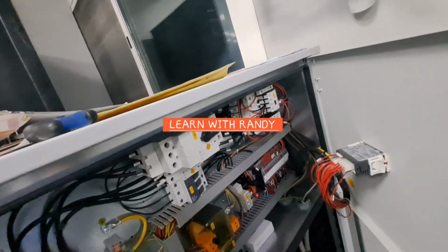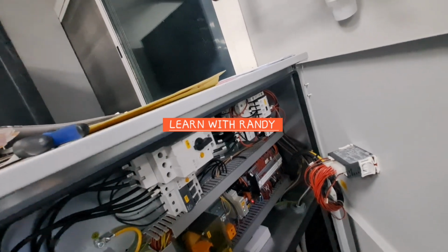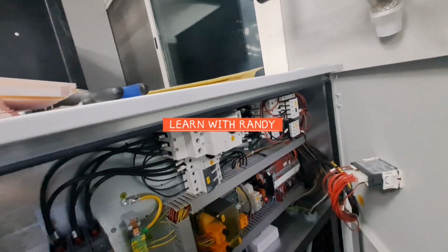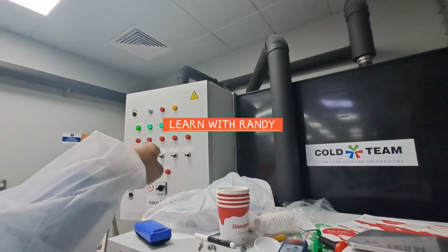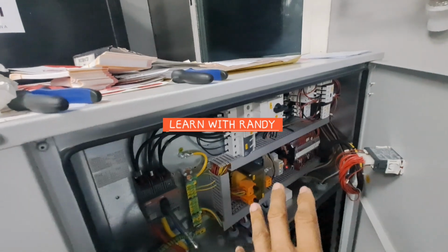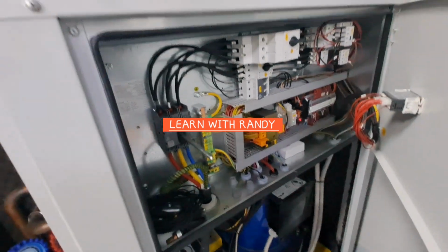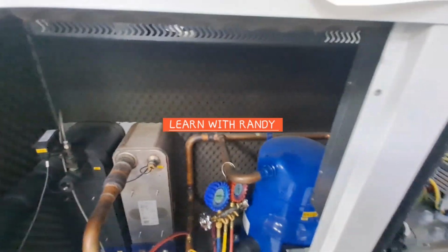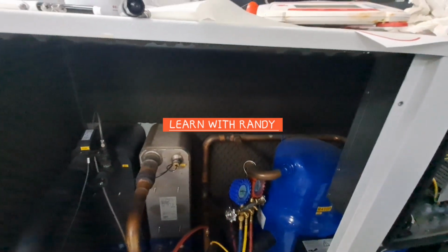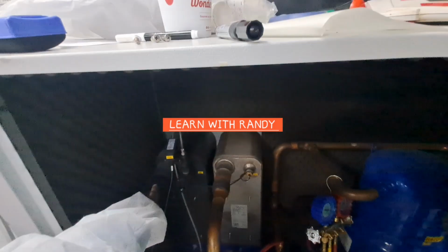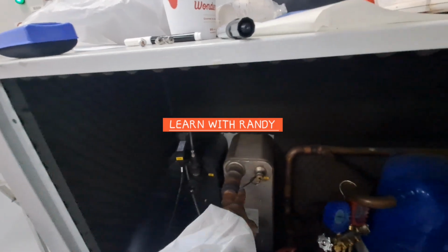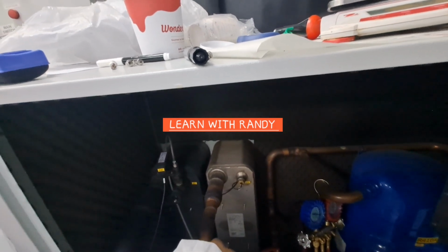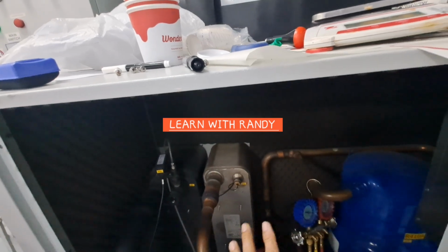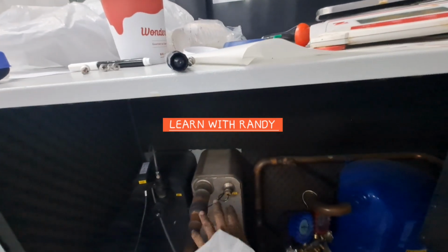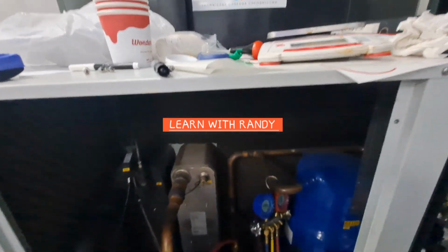So basically when you start the unit, it will collect all the inputs. If all the inputs are okay, there is interlocking that needs to be on first. Once it is on, this can be started. So it will start 2 compressors, and then the refrigeration system will kick in to cool. Again, this is for cooling the chilled water, and this is for cooling the discharge or return gas. There is no condenser. For this design, they are using a heat exchanger plus the cooling tower.